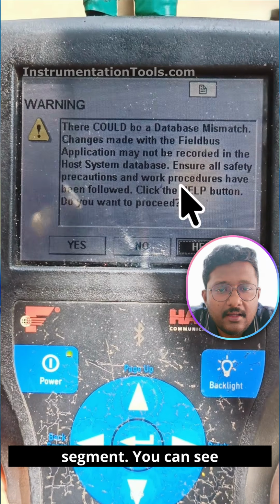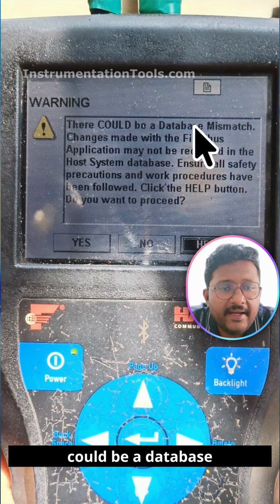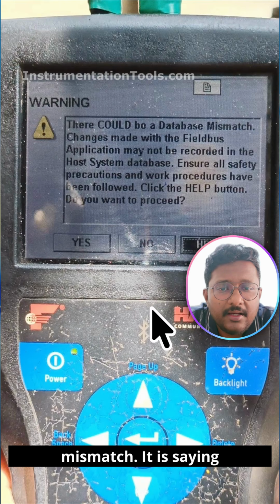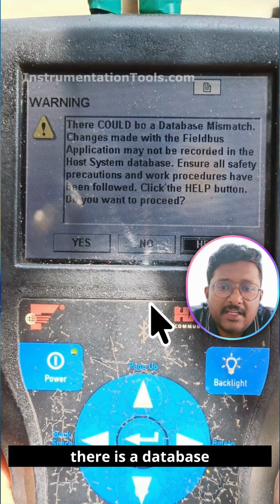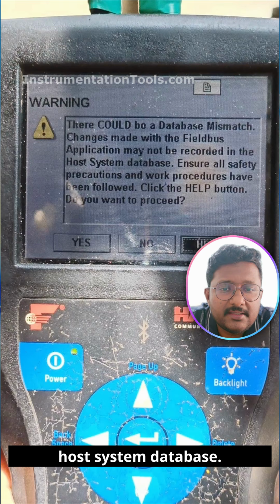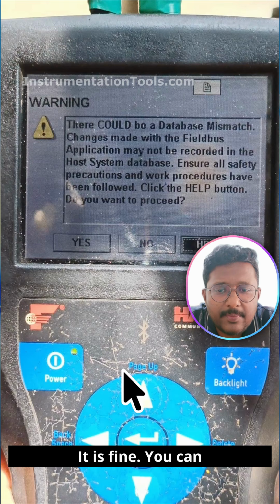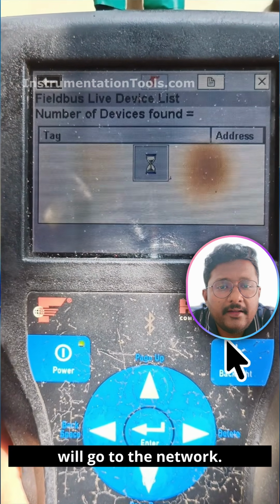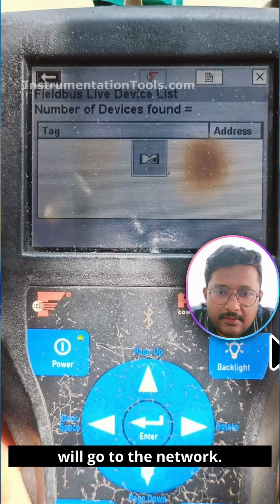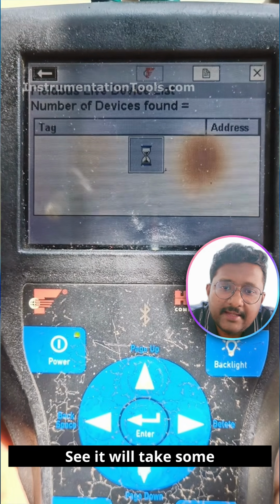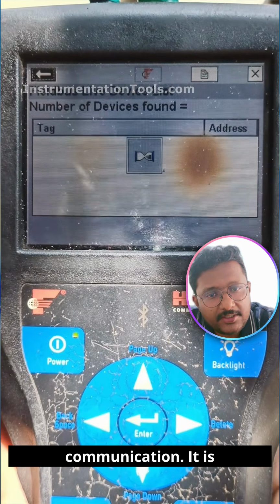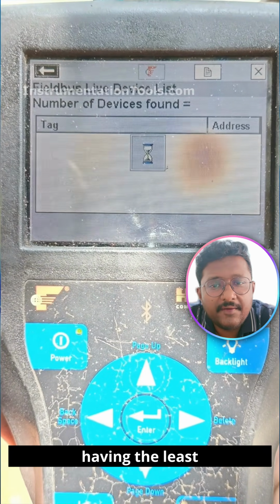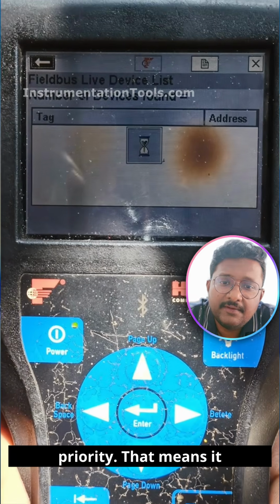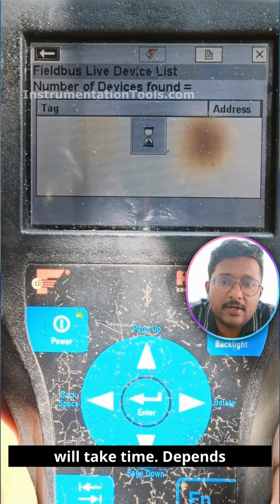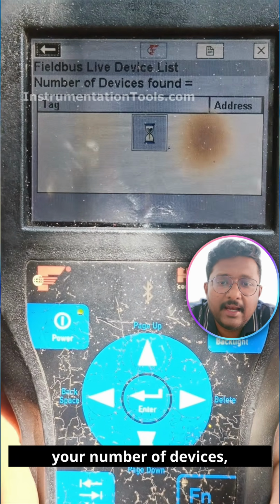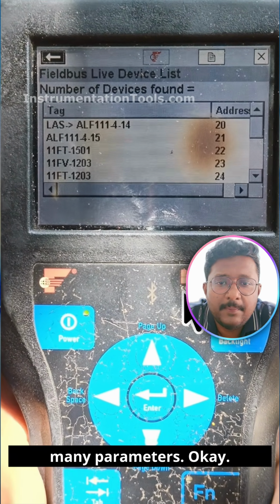on the segment. See, there is a warning. There could be a database mismatch. It is saying that there is a database mismatch with your host system database. It is fine. You can press YES, no issue. And then it will go to the network. See, it will take some time. It is acyclic communication. It is having the least priority. That means it will take time, depending on your number of devices, length of the cable, so many parameters.